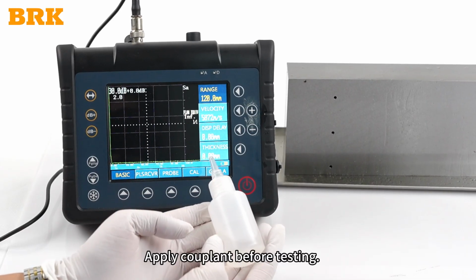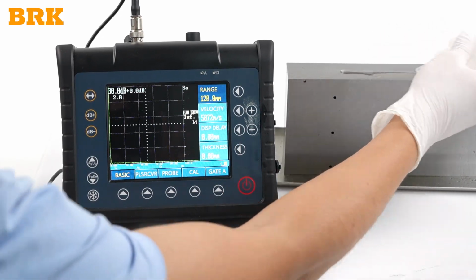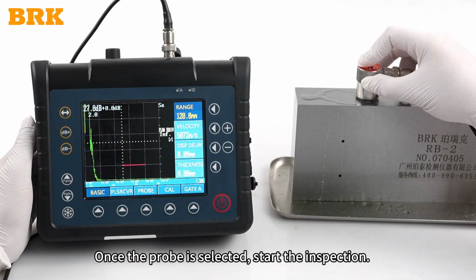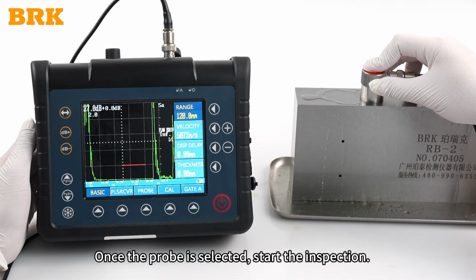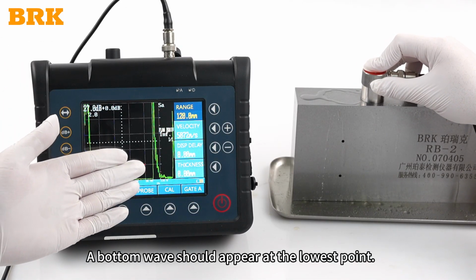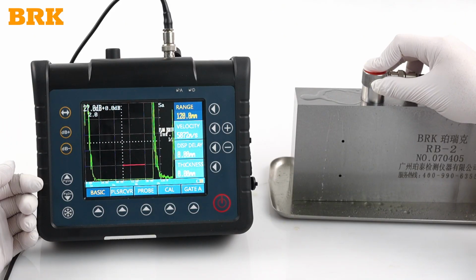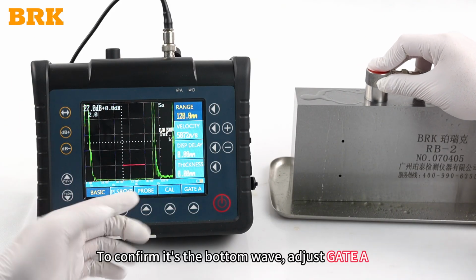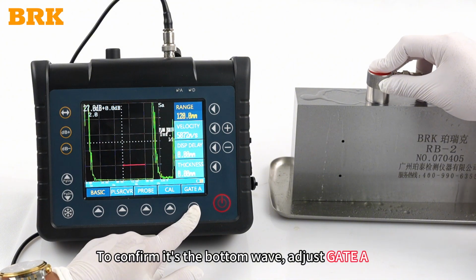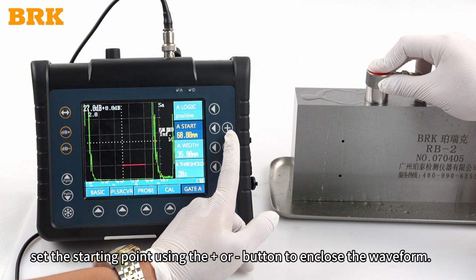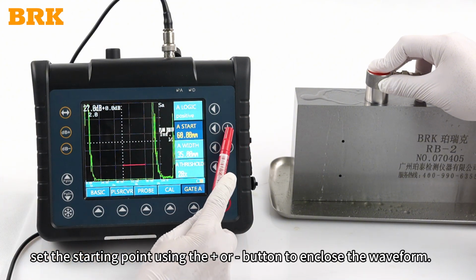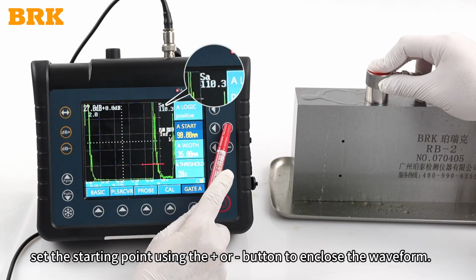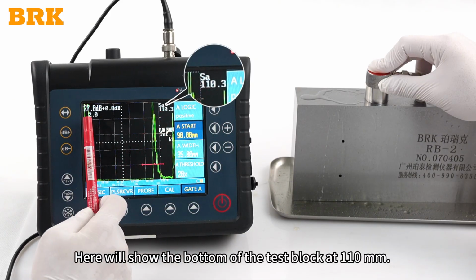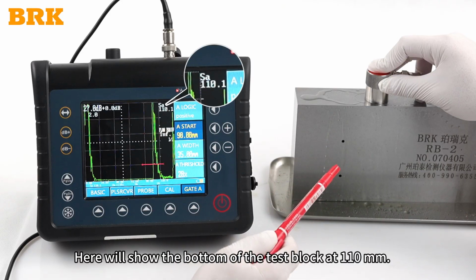Apply couplant before testing. Once the probe is selected, start the inspection. A bottom wave should appear at the lowest point. To confirm it's the bottom wave, adjust gate A. Set the starting point using the plus or minus button to enclose the waveform. Here we'll show the bottom of the test block at 110 millimeters.